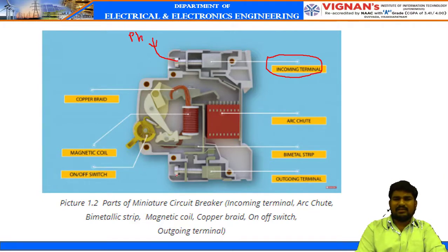and at the end of this MCB, the same wire will be returned. Basically, we use the switching operation in the phase terminal only. For example, if it is single phase, we use it only in the phase, or if it is three phase, we need to use 3 MCBs, one for each phase. So this is the incoming terminal and this is the outgoing terminal to connect electrical wires.